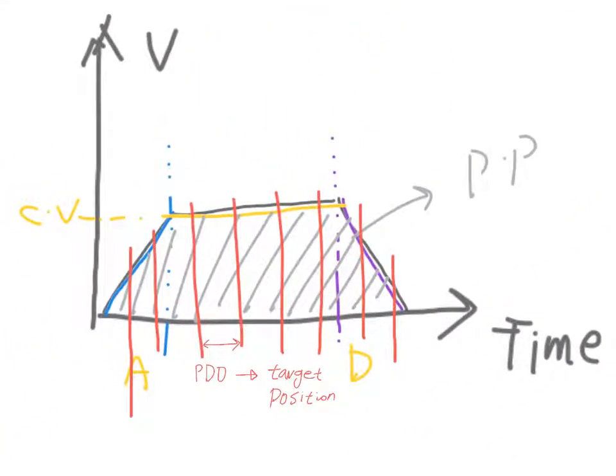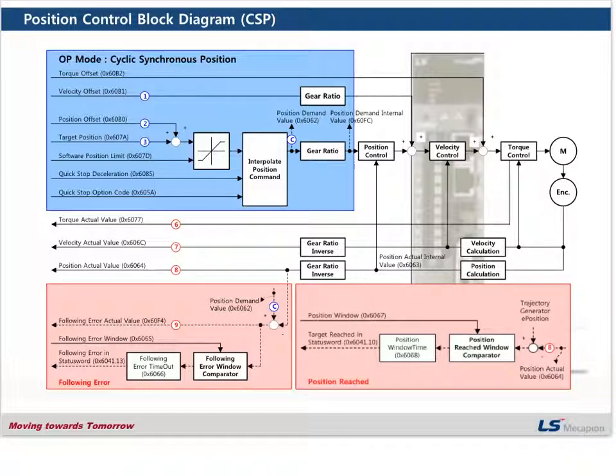The correct mode selection depends on the system circumstance. For example, if the system does not have stable communication between the master and drive, maybe PP mode will be the better option. This is the basic diagram of CSP mode — it shows the operation process of CSP. I'm not going to explain all steps here, but I would like to check the parameters which are required to be set for position control and their functions.